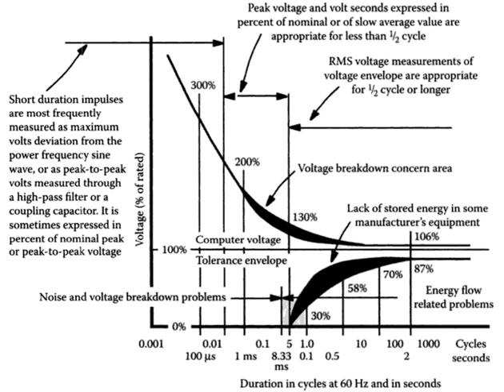Topic: Power conditioning. Power conditioning is modifying the power to improve its quality. An uninterruptible power supply can be used to switch off of mains power if there is a transient, temporary condition on the line. However, cheaper UPS units create poor quality power themselves, akin to imposing a higher frequency and lower amplitude square wave atop the sine wave. High-quality UPS units utilize a double conversion topology which breaks down incoming AC power into DC, charges the batteries, then remanufactures an AC sine wave. This remanufactured sine wave is of higher quality than the original AC power feed.